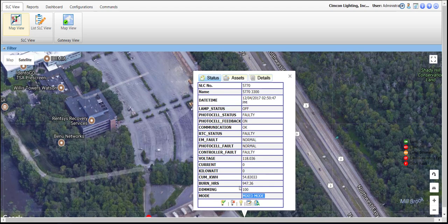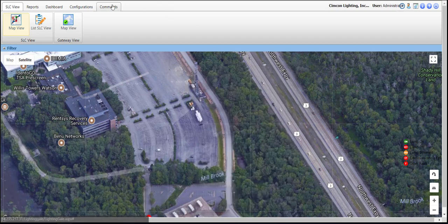In order to turn lights on, off, or to dim them, the controllers must first be set to manual mode. To do this, we will want to navigate to the Commands tab across the top, go to Mode, and Set. We want to select Manual Mode.